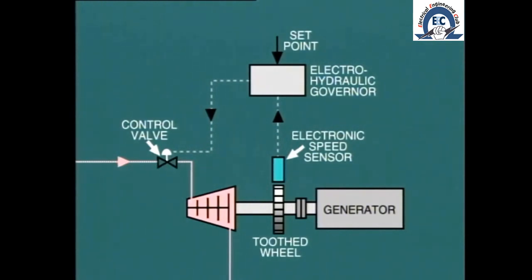The electronic signal is then processed and converted into a mechanical output that operates the pilot valve in the normal manner. In these governors, the set point and other adjustments are inputted electronically to the processor.